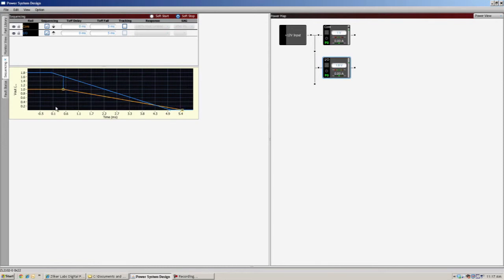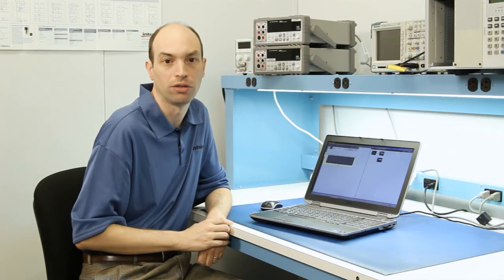The first rail starts dropping. Once it reaches its power good threshold, the falling threshold, it sends a signal across the DC bus to the core, and then that rail will begin its shutdown process.